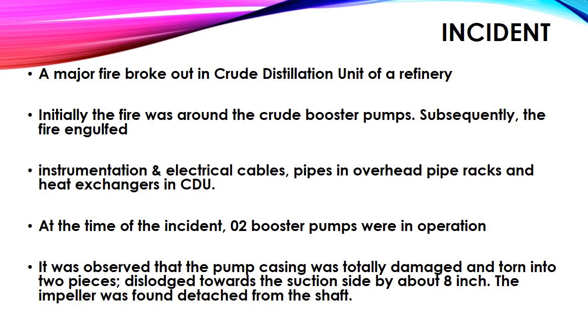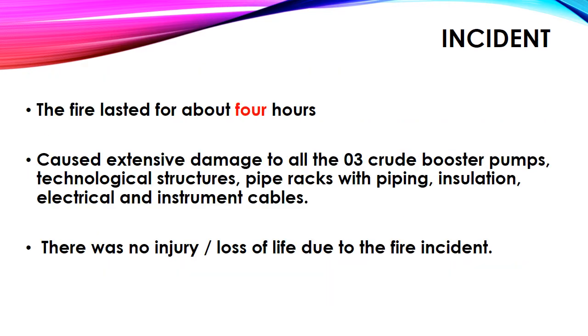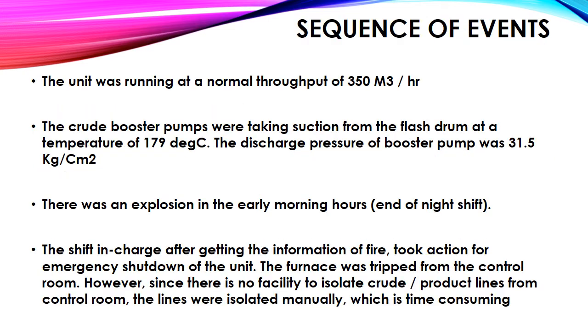At the time of the incident, two booster pumps were in operation. It was observed that the pump casing was totally damaged and torn into two pieces, dislodged towards the suction side by about 8 inches. The impeller was found detached from the shaft. The fire lasted about 4 hours and caused extensive damage to all three crude booster pumps, technology structures, pipe racks, piping, insulation, electrical and instrument cables. There was no injury or loss of life due to the fire incident.